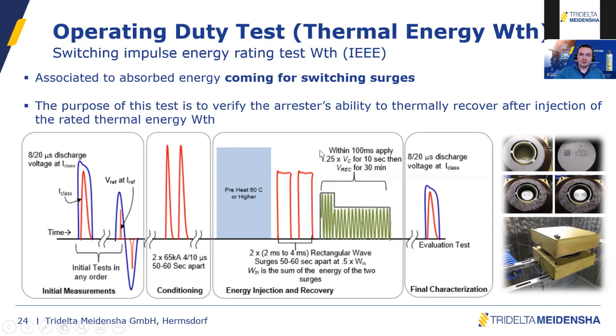After the energy injection, the arrester needs to recover. After injection, the temperature is quite high, and then you have to apply the rated voltage for 10 seconds, and then the maximum continuous operating voltage for 30 minutes. You want to make sure that the temperature is going down. That's why we say this test is to verify the thermal recovery. Afterwards, as is very typical, you repeat the residual voltage test to make sure that there is no change in the protection properties.